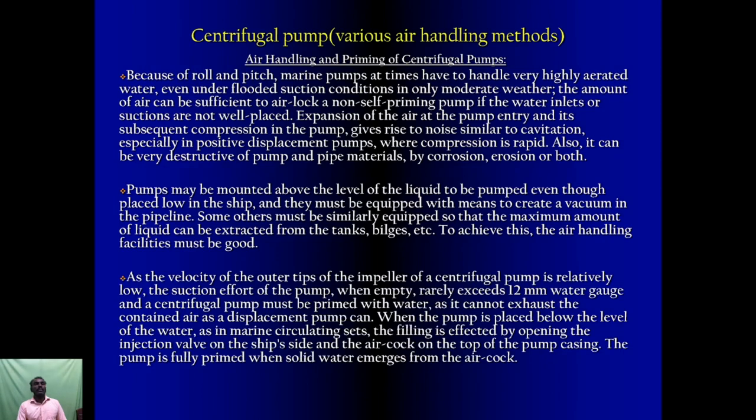Pumps may be mounted above the level of the liquid to be pumped, even though placed low in the ship, and they must be equipped with the means to create a vacuum in the pipeline. Some others must be similarly equipped so that the maximum amount of liquid can be extracted from the tanks, bilge, etc. To achieve this, the air handling facilities must be good. As the velocity of the outer tips of the impeller of a centrifugal pump is relatively low, the suction effect of the pump when empty rarely exceeds 12 mm water gauge, and a centrifugal pump must be primed with water as it cannot exhaust the contained air as a displacement pump can.